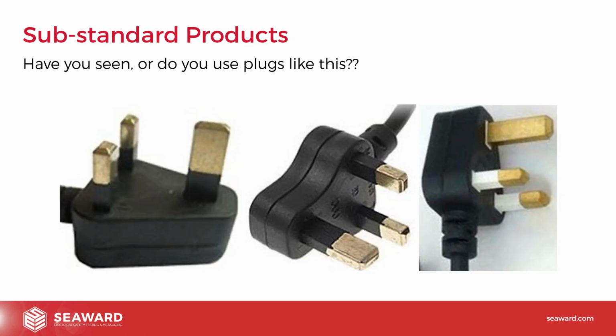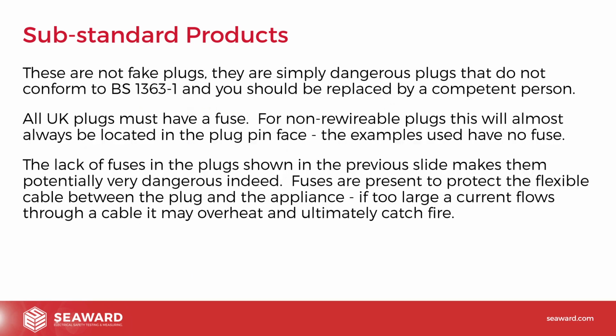Now, have you seen plugs like this? These are unfused plugs. So again, we've got unfused plugs, the size of them, the size of the pins, the clearance distances to the edge of the plugs, and even on the first 2 there, you can see that they've actually got a half-sleeved earth pin. So again, the half-sleeved earth pin causes us big problems. It doesn't comply with any standards, and when used with Class 1 equipment, it could actually obstruct the earth path and mean that the Class 1 protective measure, the protective earthing, doesn't actually work on that equipment. So again, these can be very dangerous.